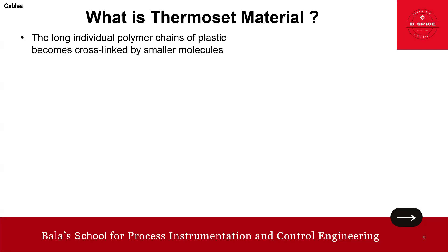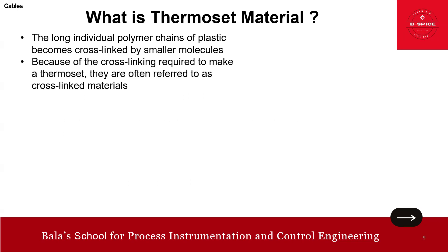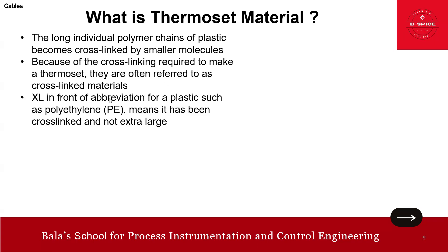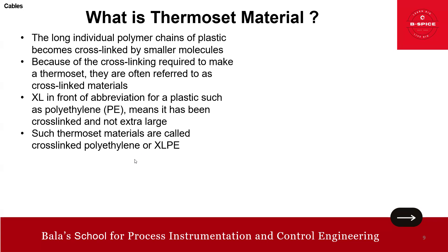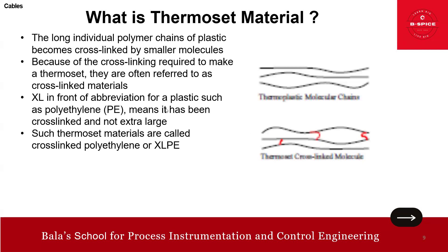The long individual polymer chains of plastic become cross-linked by smaller molecules. Because of the cross-linking required to make a thermoset, they are often referred to as cross-linked material. The 'XL' prefix in abbreviations for plastics such as polyethylene — that is XLPE — means it has been cross-linked, not 'extra large'. Such thermoset materials are cross-linked polyethylene or XLPE. So thermoplastic does not have cross-linking; thermoset does have cross-linking.